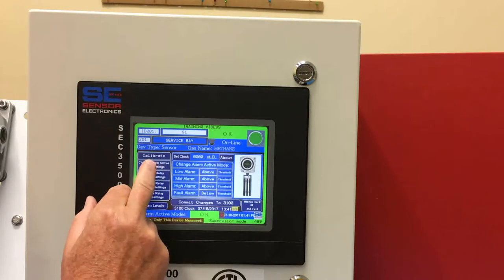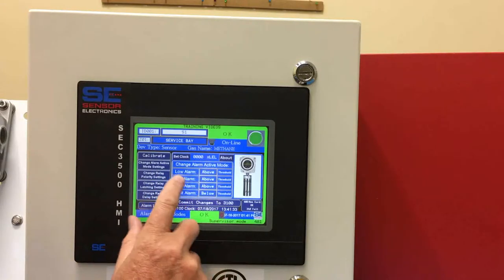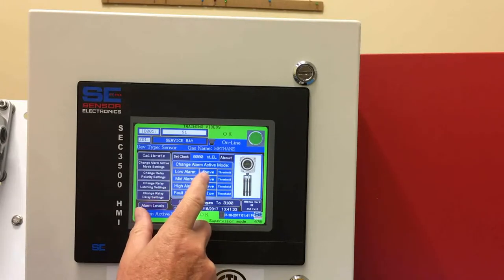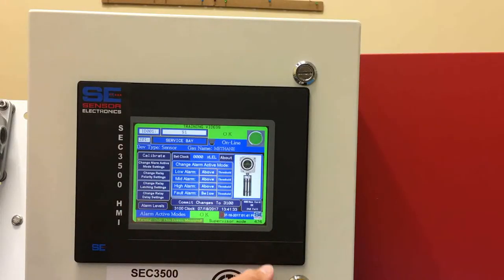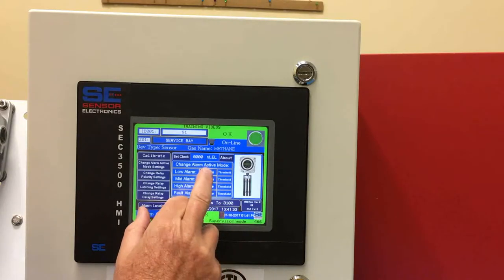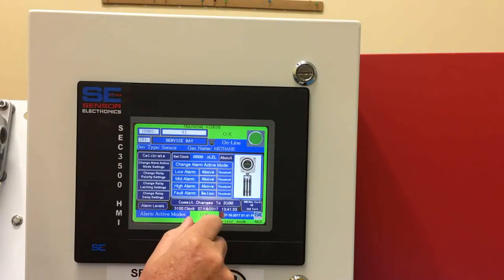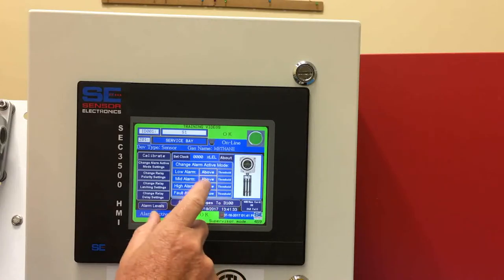We also have the option of selecting active alarm modes. Basically, once the low alarm relay set point — which was set for 20 — goes above that threshold, it would enable the relay or the alarm condition at the 3500. You can also set it for below if you want it on the dropping edge, but in 99% of cases it's going to be above.